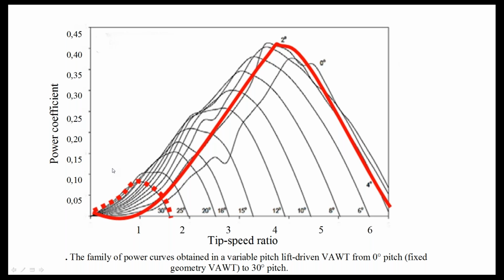But in the startup region, shown by the red bold curve, you have negative or zero power coefficient, and you need a variable pitch, for instance of 30 degrees on the blade axis, to achieve, as shown in the red dotted curve, sufficient torque to start the turbine.